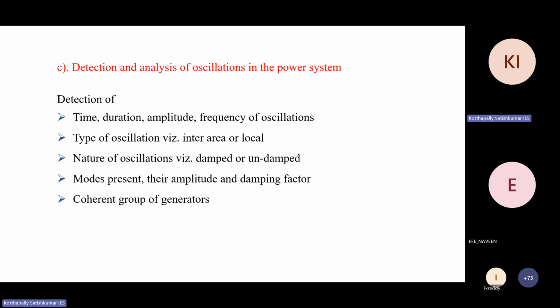There is the type of oscillation, whether inter-area or local oscillations, and the nature of the oscillation, whether it is undamped or damped, and the modes present, their amplitude and damping factor, and the coherent group of generators. Coherent group means for a fault, a few generators will exhibit the same behavior while others will not. So you can identify the coherent group of generators from this data.